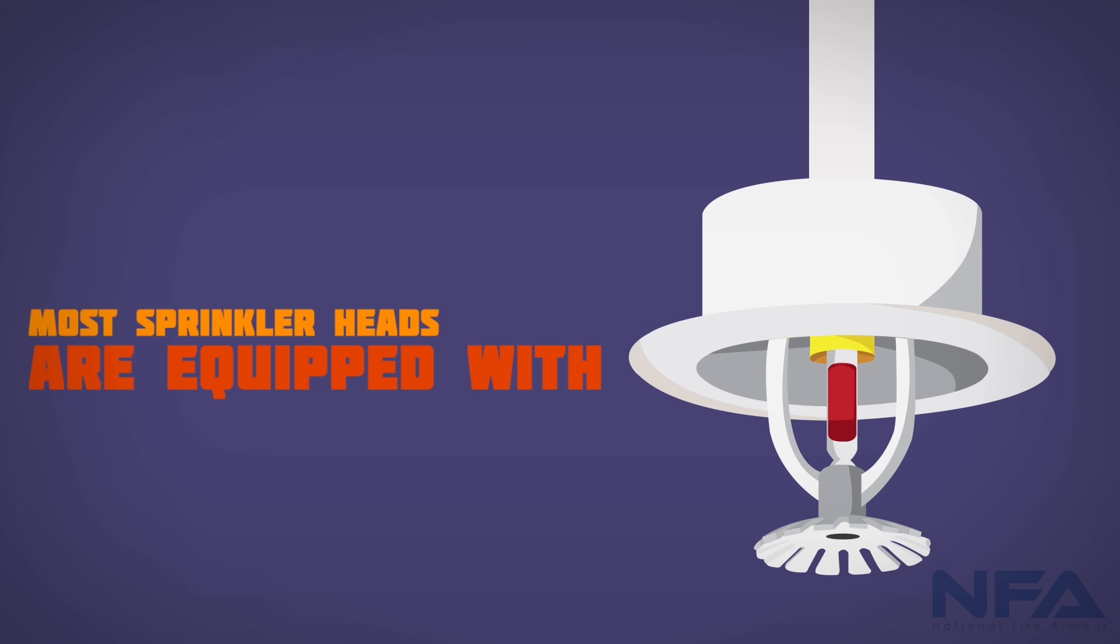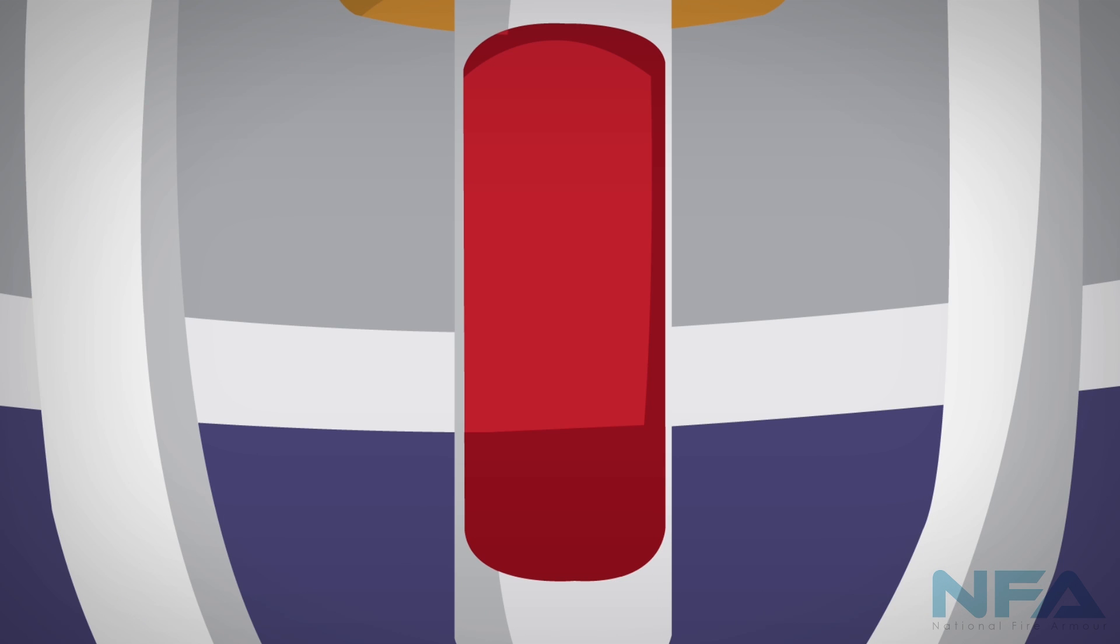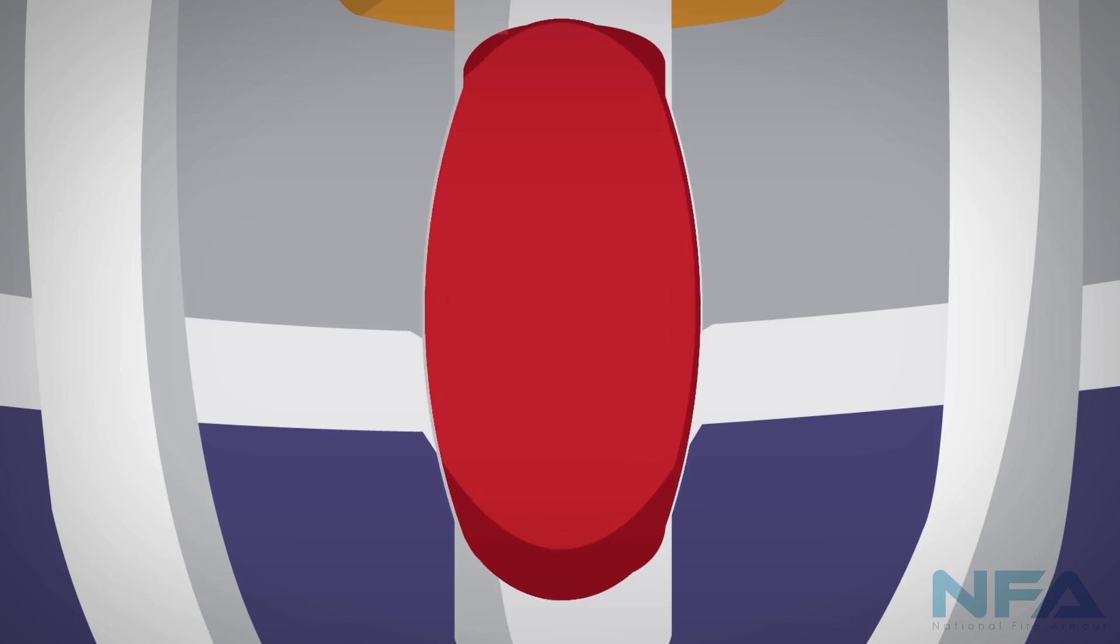Most sprinkler heads are equipped with a glass trigger filled with a glycerin-based liquid that expands at the appropriate temperature, breaking the glass and activating the sprinkler head.